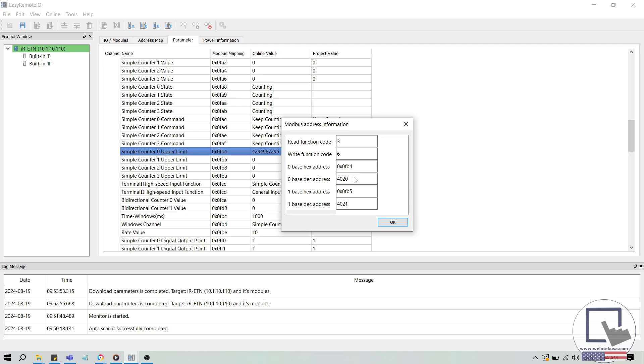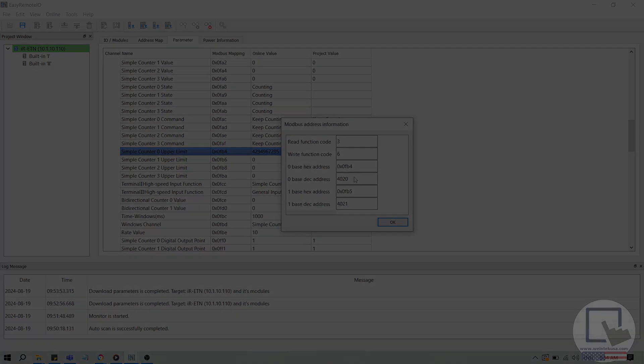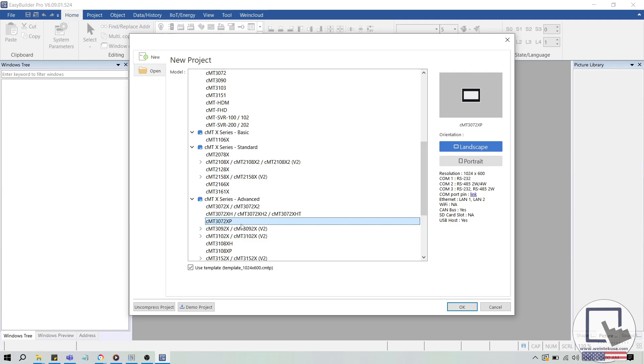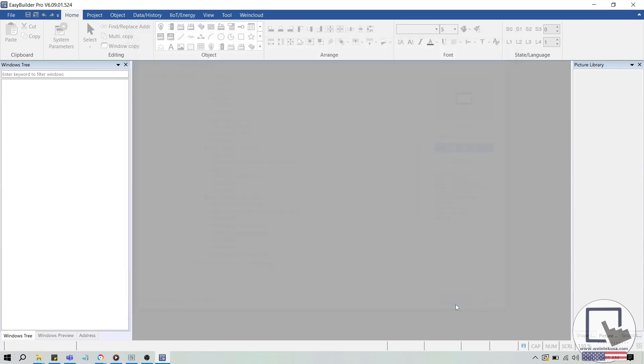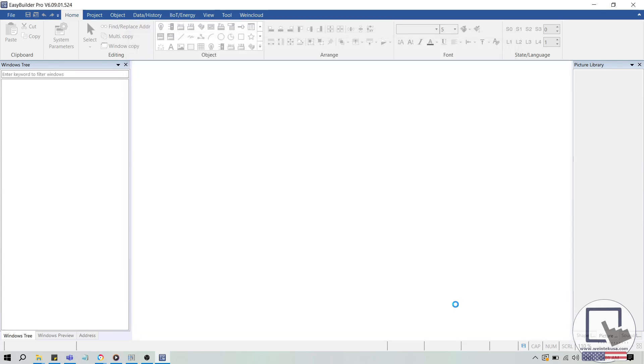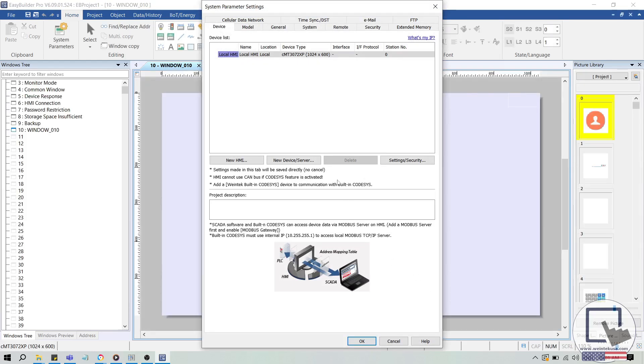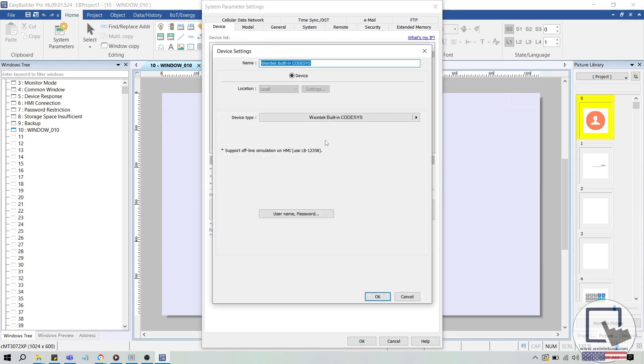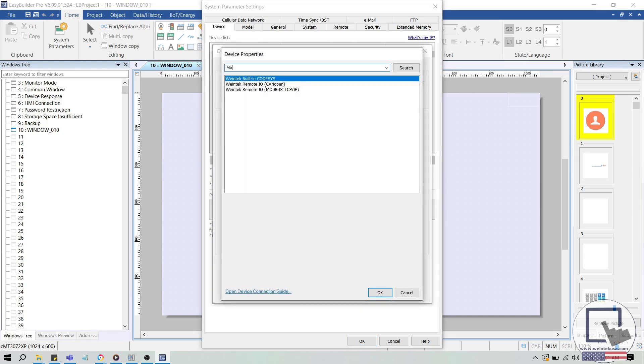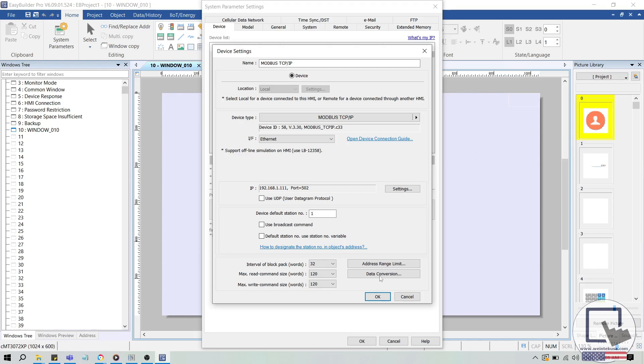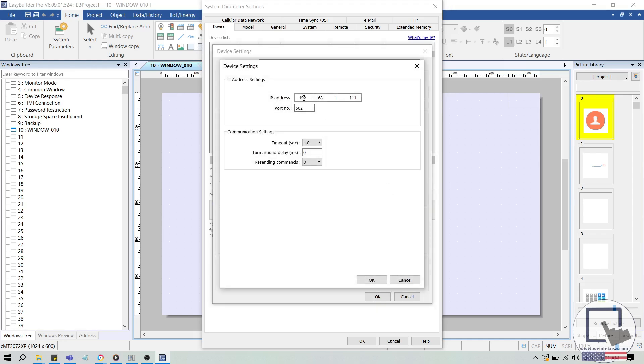Let's use EasyBuilder Pro, Weintek's HMI software, to read some of these parameters. I'll create a new project for a CMT 3072 XP. In the system parameters, I'll select the new device slash server button and add our Modbus TCP IP driver. Once added, I'll use the settings button and ensure that the IP address of the Modbus TCP IP driver matches the IP address of the IR ETN 40R.